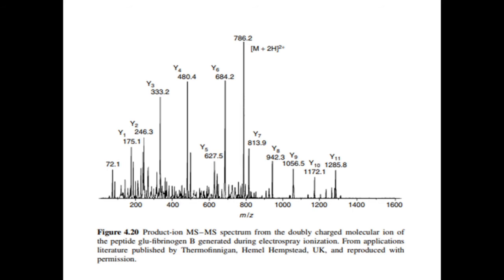Summary for the electrospray interface: the advent of the electrospray interface has allowed the full potential of LC-MS to be achieved. It is probably the most widely used LC-MS interface as it is applicable to a wide range of polar and thermally labile analytes of both low and high molecular weight, and it is compatible with a wide range of HPLC conditions.